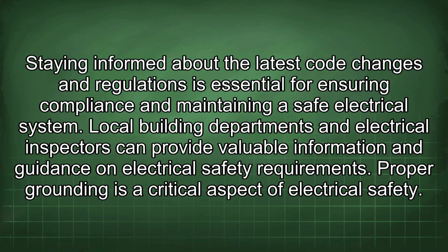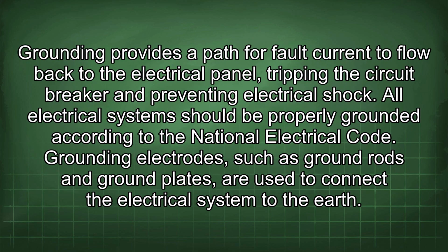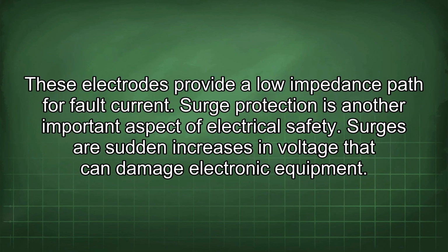Proper grounding is a critical aspect of electrical safety. Grounding provides a path for fault current to flow back to the electrical panel, tripping the circuit breaker and preventing electrical shock. All electrical systems should be properly grounded according to the National Electrical Code. Grounding electrodes, such as ground rods and ground plates, are used to connect the electrical system to the earth. These electrodes provide a low impedance path for fault current.